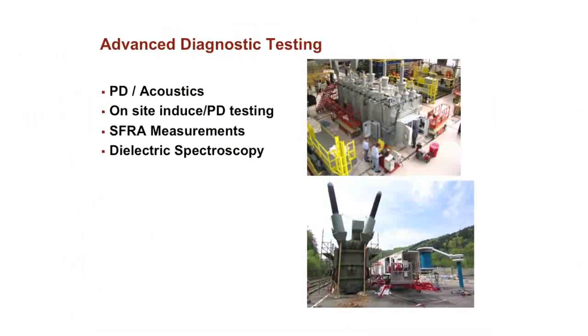Okay, so for advanced diagnostics, you would normally do this when you think there's a problem with the transformer. Say there's gassing that indicates some kind of issue. One thing that can be done is online partial discharge measurement. This is where you put acoustic equipment on the transformer and try to triangulate to where there could be some issue. You could also do offline partial discharge testing. This is where you take the transformer offline, bring equipment in, and put an overvoltage on the transformer. It could be 130% of normal rated voltage.